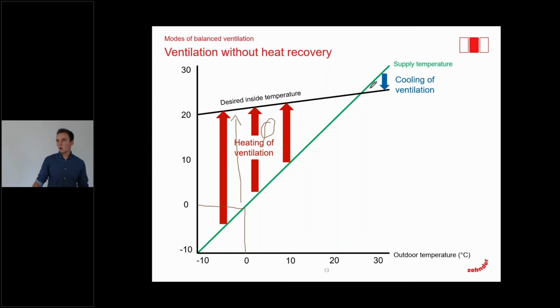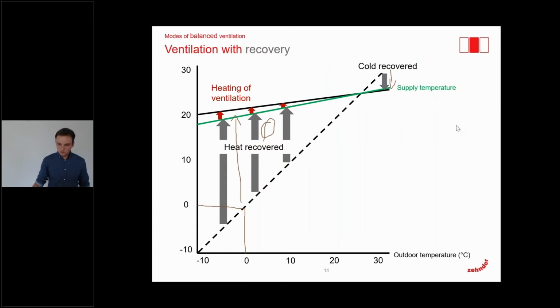And the same applies in summer or in warmer regions. Here we need to cool down the air to get to our comfortable level. Now, what happens if we build in a heat recovery? There you can see the supply air temperature is very close to the desired air temperature due to the heat recovery. Let us do the same example, 0 degrees outside. And then we get it on a higher level due to the heat recovery.